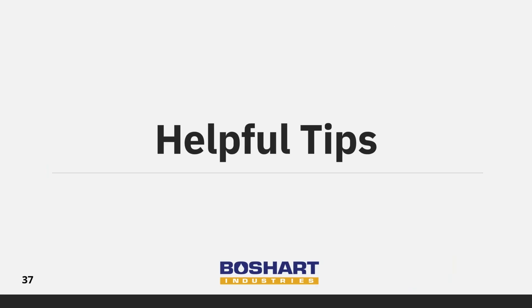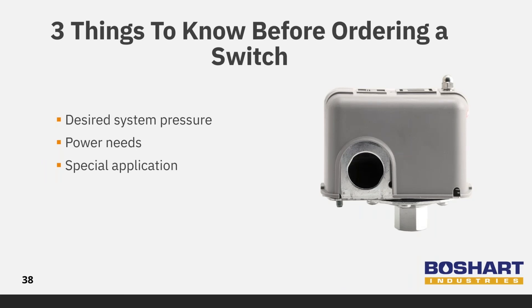Now we will look at some helpful tips. Here are three things to know before ordering a switch. First, you need to know your desired system pressure — this covers the cut-in, the cut-out, and the differential. Second, you need to know your power needs; look at the pump for what sort of power is going to go through the switch. Third, you need to know if you need a special application switch, like a low-pressure cut-off switch, for example.